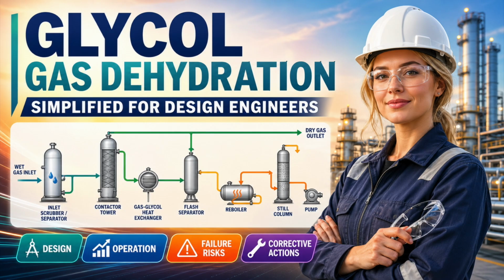Many so-called pump failures are not pump failures. They are suction system failures. Replacing the pump repeatedly will not correct poor static head, gas accumulation, excessive friction, or a dirty strainer.